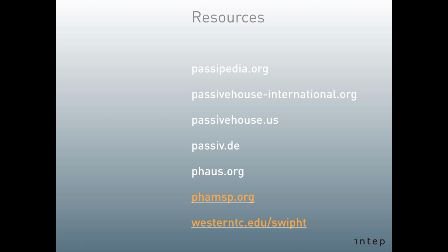Can you talk about your decision a little bit to go with the ducted models that don't go to as low a temperature? That's a great question, Rolf. So the question was, why did we go with a ducted heat pump and not a single split? Because a single split can actually provide a COP down to lower outdoor temperatures than the system that we chose. And the answer is quite simply the distribution dilemma. One of the things that we find is that single point source distribution, even in a passive house with a kick-ass building envelope, is problematic, mostly on the cooling side, but somewhat on the heating side.